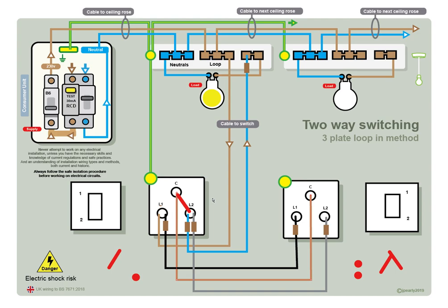And it's just got to move it really, it's quite simple. Black is in L1, so to solve the issue you put black back in L1. And the brown is in common, I put brown in common. We've got two browns, so we've got this brown coming in, we've got that brown as well. So you know it takes a bit of working out sometimes. Sometimes people sleeve the switch conductors brown conductor as well, so you know what that's doing, you know it's a switch conductor, not a permanent live. That can help.